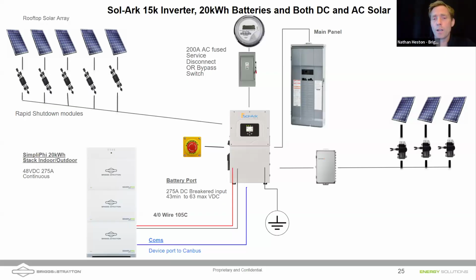With the Sol-Ark 15K, you can bring in up to 19 kilowatts of AC coupled solar, 19.2. And on the DC side of things, you can bring in an additional 15 kilowatts of continuous DC power in. Now, there are some limitations when you're doing both, but the AC limitation is really occurring from the AC bus of the inverter, and the DC limitation is occurring on the DC side of the inverter. So they're somewhat independent of each other. Of course, when you're coupling to loads, you have to pay attention because you would be using the AC bus with the DC side.